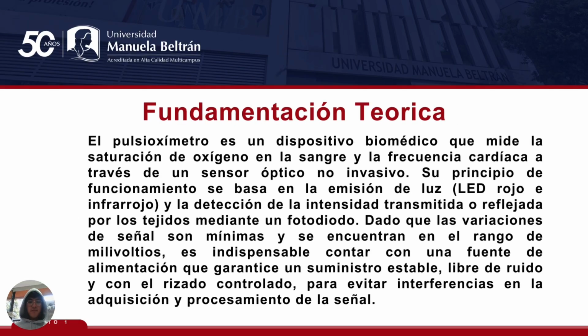The pulse oximeter is a biomedical device that measures blood oxygen saturation and heart rate using a non-invasive optical sensor. It works by emitting red and infrared light and detecting the transmitted or reflected intensity through the tissues with a photodiode. Since the signal variations are very small, in the millivolt range, it is essential to use a power supply that provides a stable output, low noise, and controlled ripple to avoid interference in signal acquisition and processing.